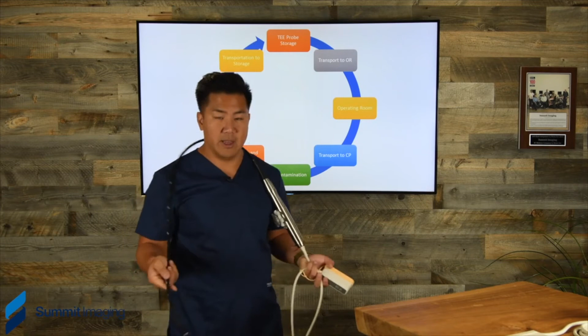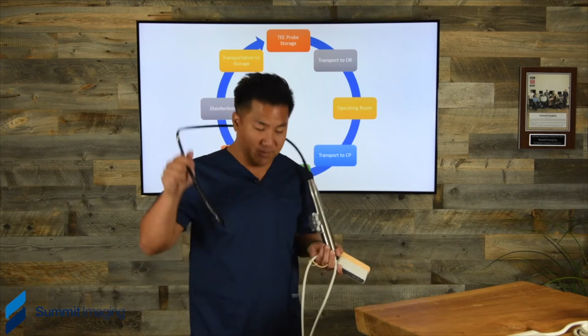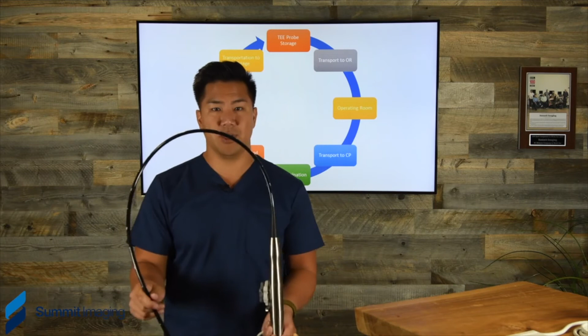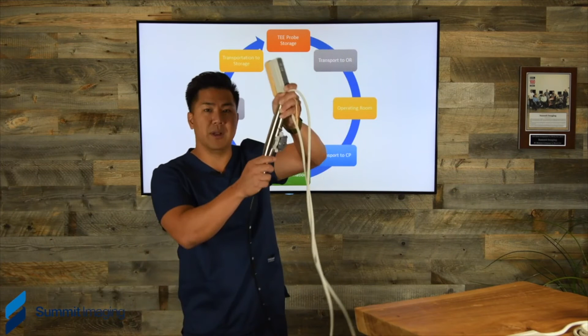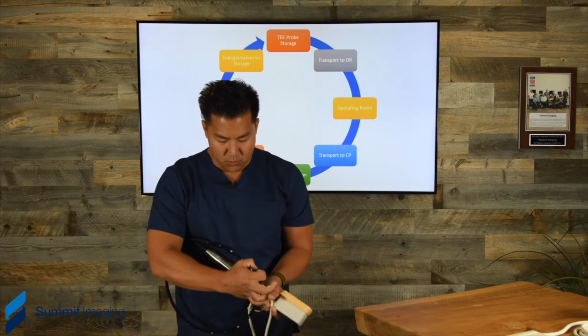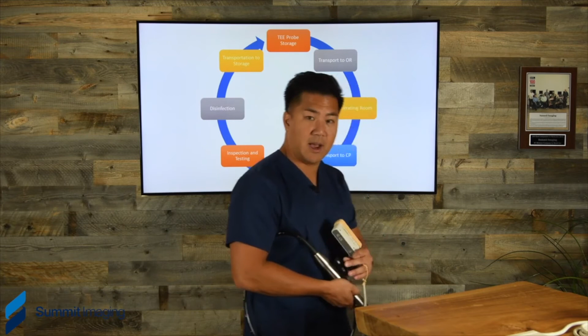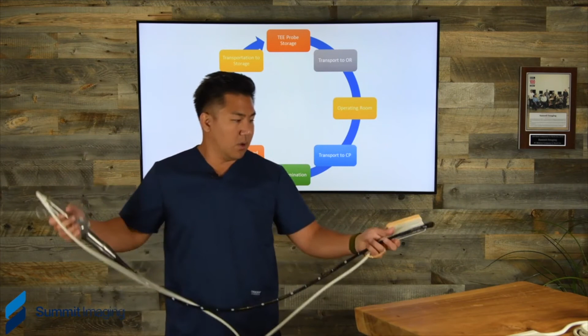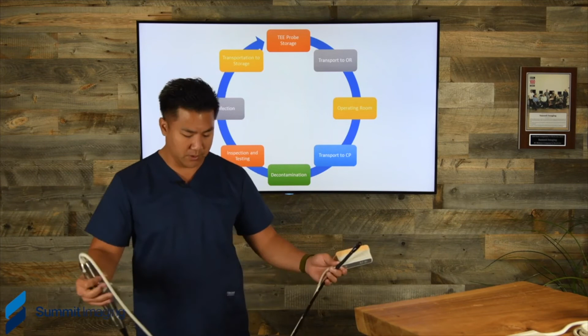And so what we've seen is everything from hospital employees trying to carry it like this, which we don't recommend because you don't want this touching you, especially after it just came out of surgery or if it just got used on a patient. You really don't want this entire insertion tube touching you at that point without the proper protective gear. We've seen people roll them up with the tip right here, and as they're walking around, the tip starts banging, as you can hear right now, on this metal casing here. We've even seen customers walking like this, and then the tip bangs on the can of the transducer. So what do we recommend?